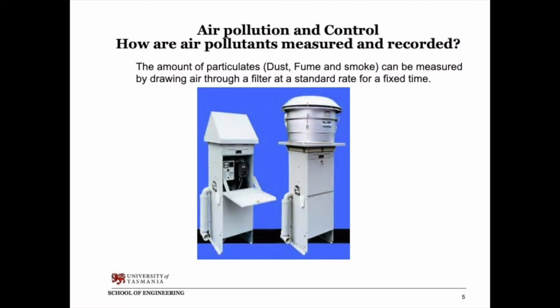So the technique is very simple. You just draw a whole lot of air through a filter at high speed, and you leave the filter running there for 24 hours, and then you take the filter paper and you weigh it, and that gives you the amount of pollutants that are trapped by a filter of that size.